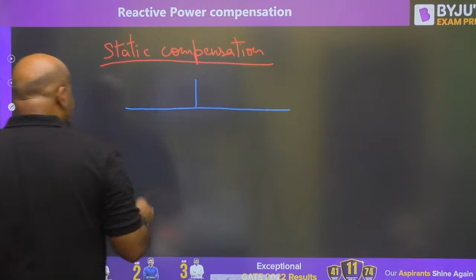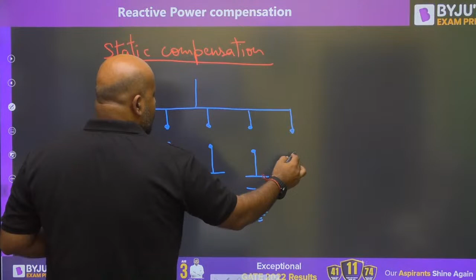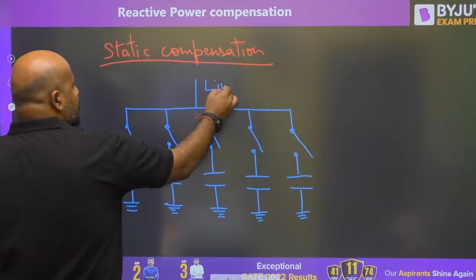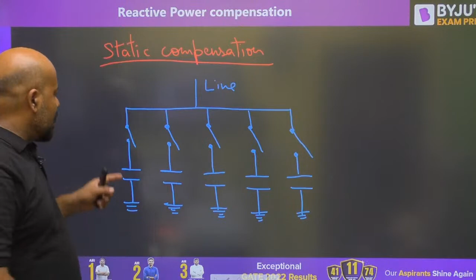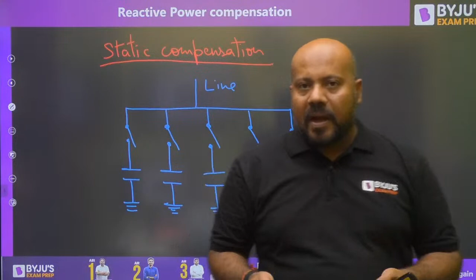Suppose this is your bus where you want to provide the reactive power compensation. And suppose you are using a shunt capacitor bank. Number of shunt capacitors we are using, something like this. These are the switches. This is your line which needs compensation, and these are your shunt capacitors connected like this. Whenever you want to provide some reactive power compensation, you want to add that capacitor, you just close the switch.